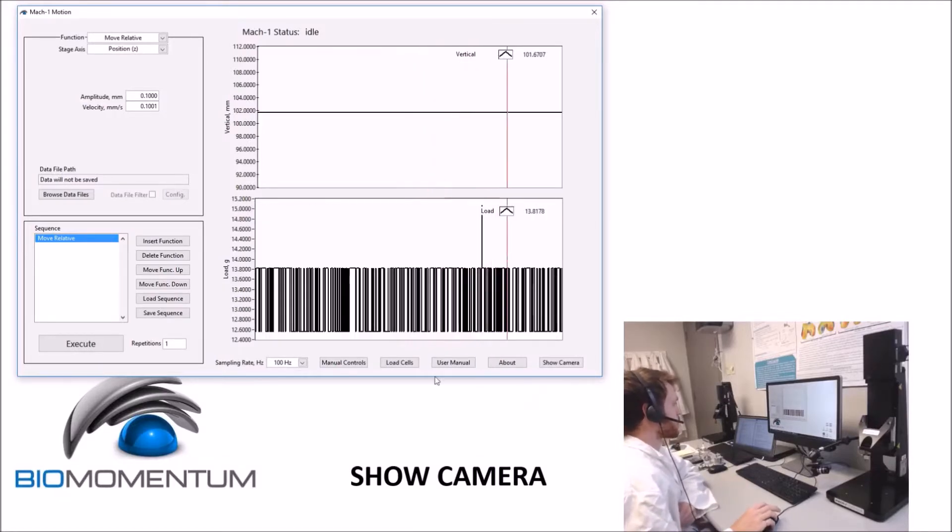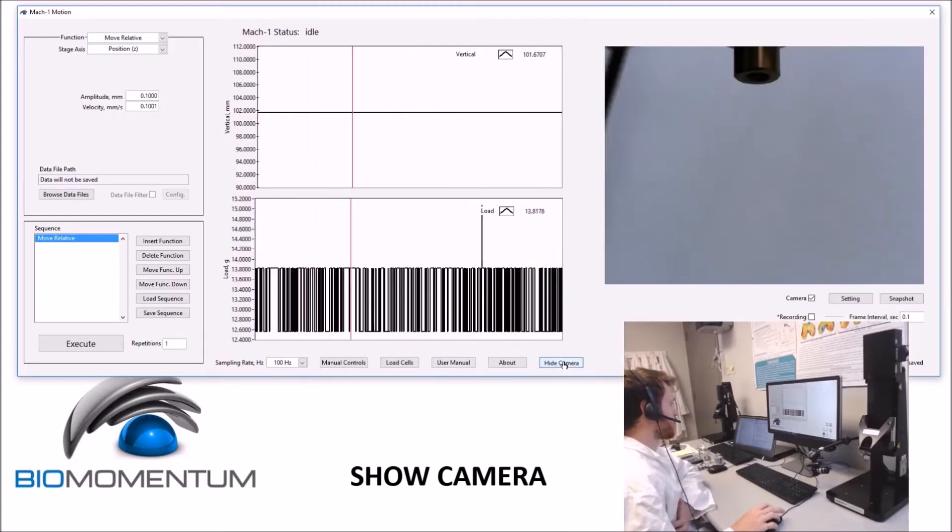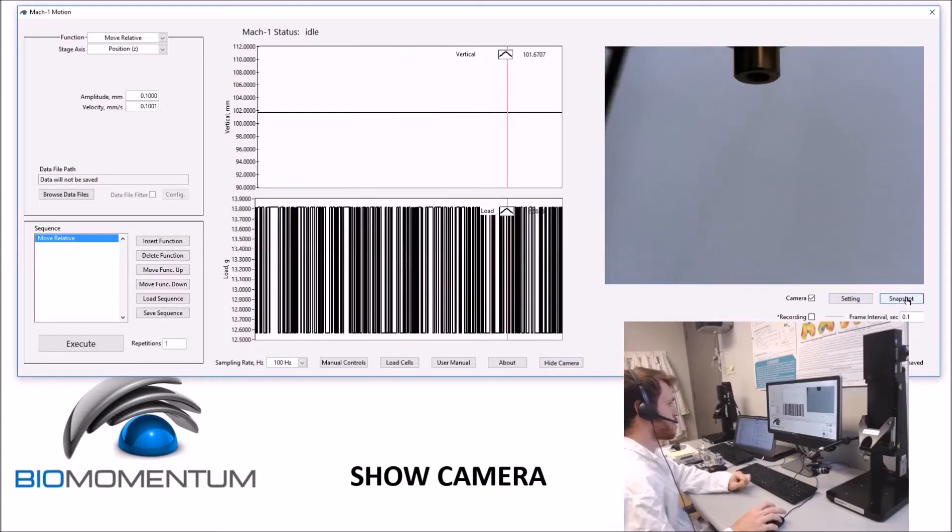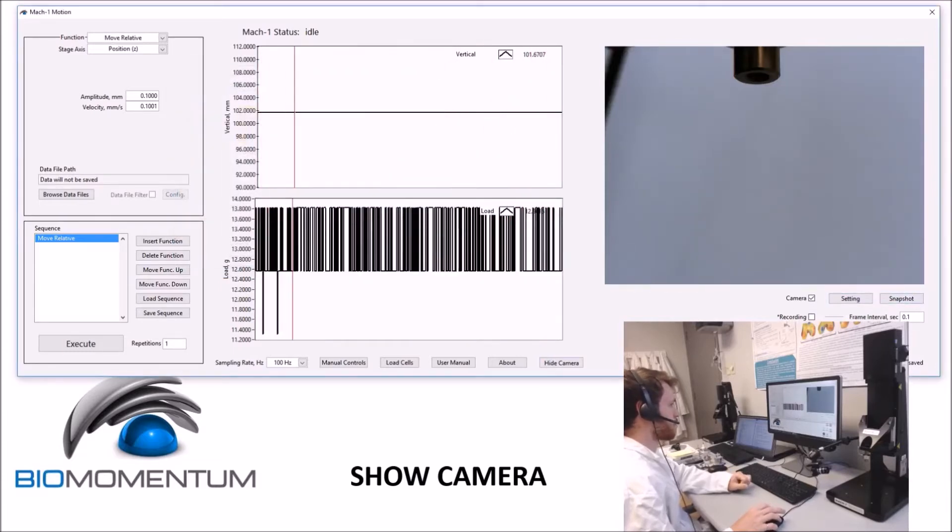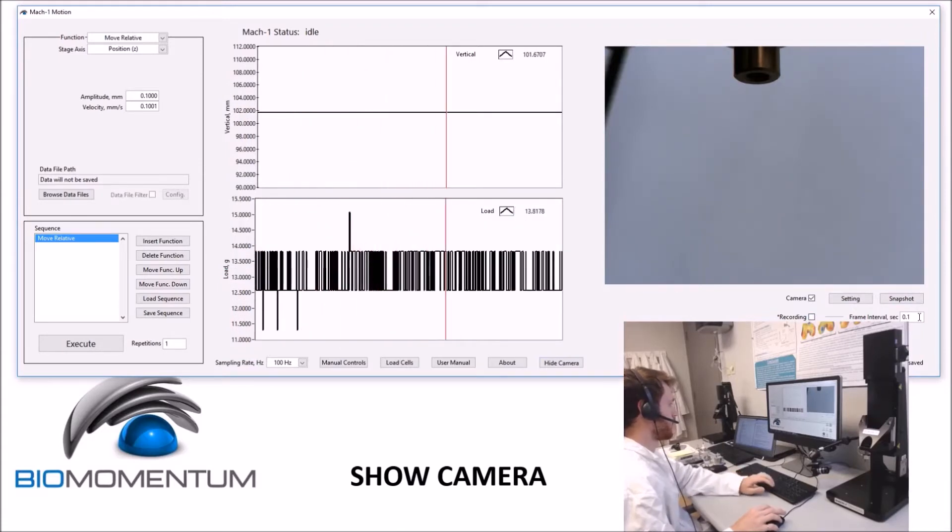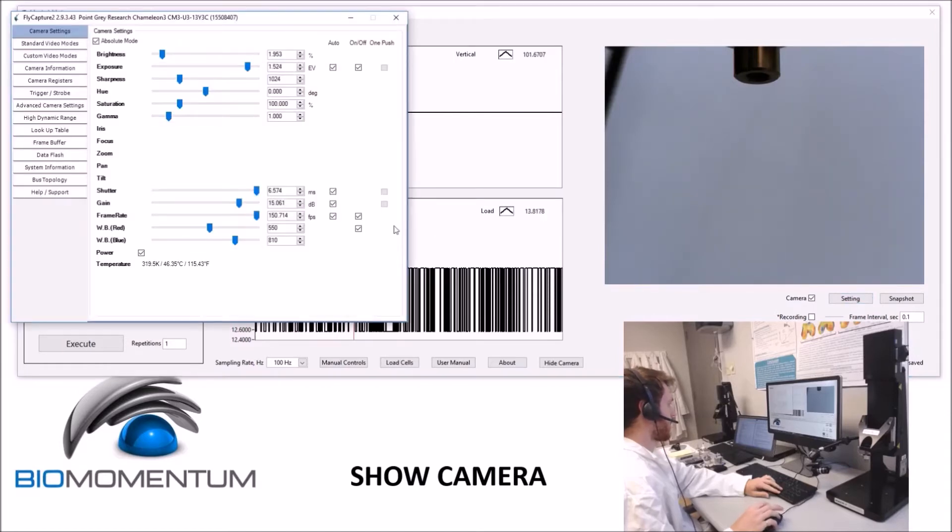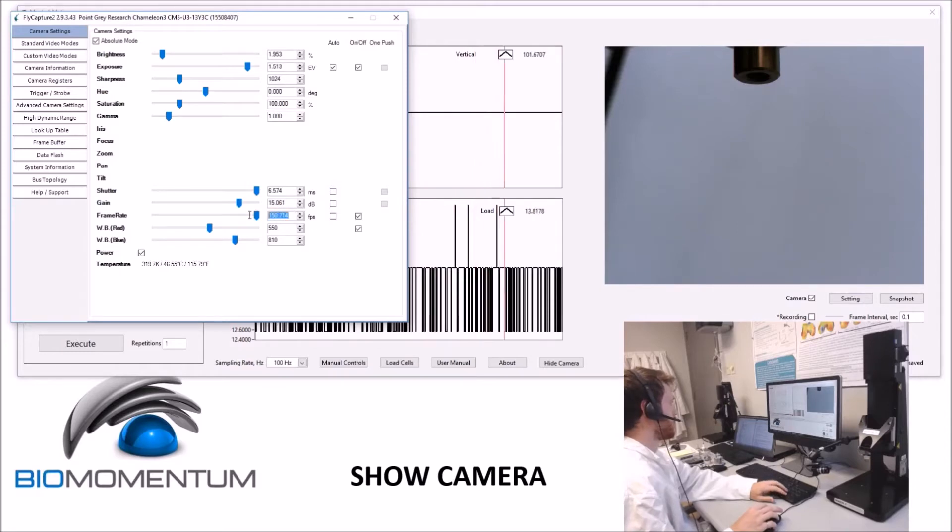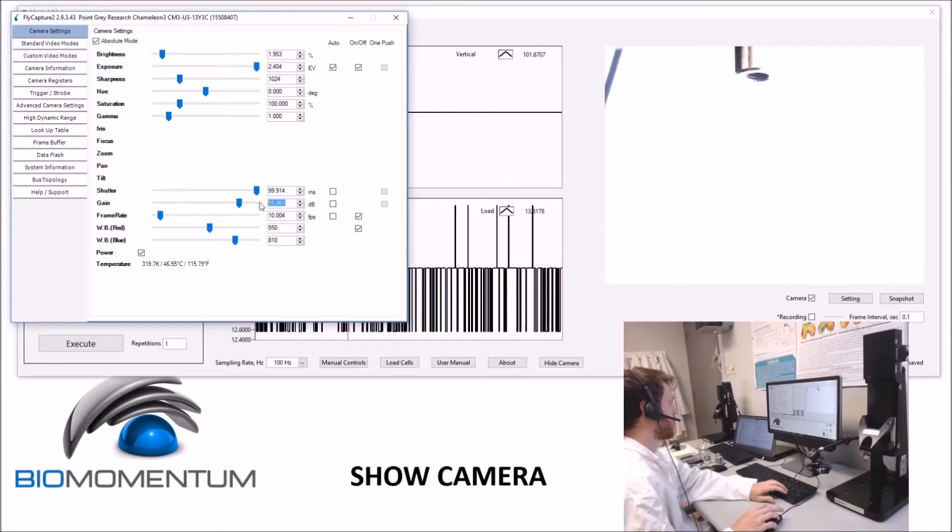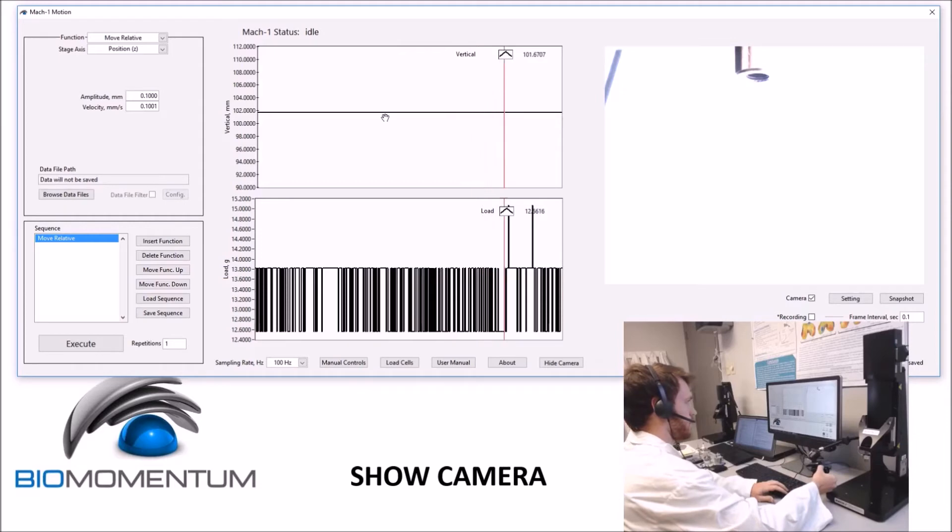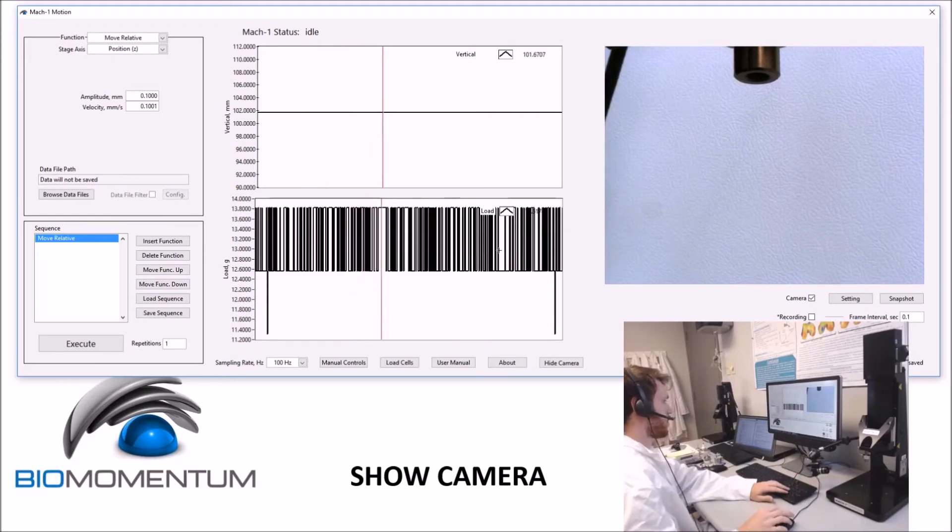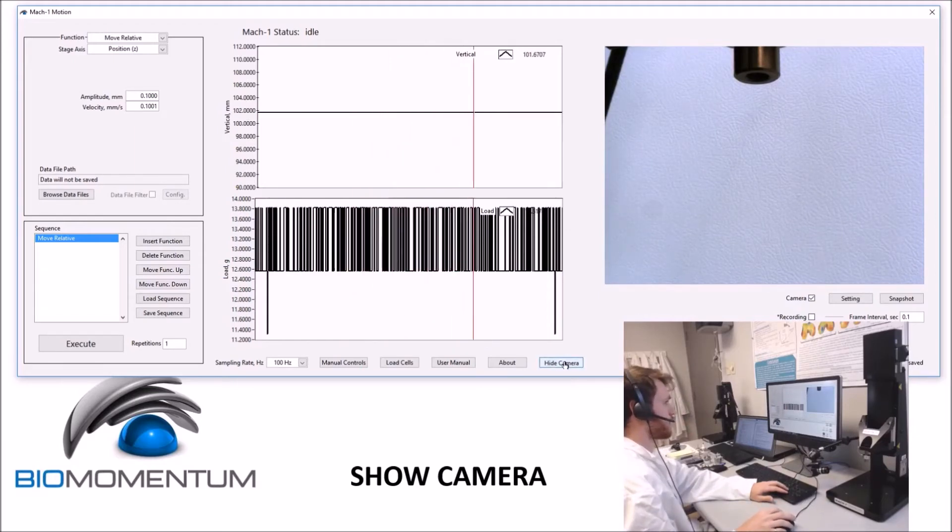A camera feed can be added to the Mach-1 so that image capture can be synchronized with the raw data of the mechanical test. Clicking the show camera button reveals a secondary panel displaying the camera feed as well as the related parameters. Clicking the snapshot button will save an image. Activating the recording checkbox will record video during data acquisition, and the frame interval is the time between saved images in the video. The minimum interval is 0.1 seconds. The ideal parameters for the camera settings are unchecking all three frame rate, gain, and shutter, setting the frame rate at 10 frames per second, the shutter at 100 milliseconds, and the gain at its maximum. You can then readjust using the lens. Clicking the hide camera button will switch back to the regular panel.